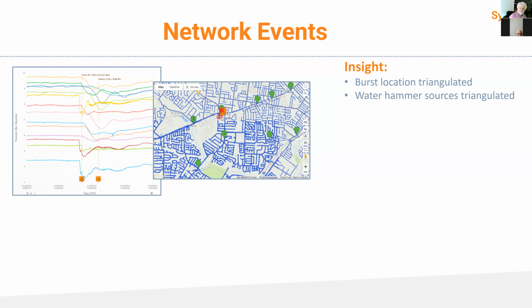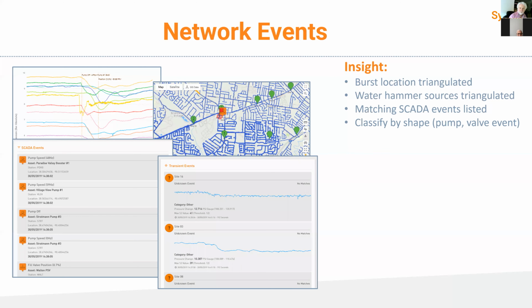The first step is we'll look at the SCADA data that we might or might not have, telling us what network activity there is. So in this case, you can see we've tagged a pump event. We'll then triangulate it, see if we can get a location. So we'll look for the onsets and triangulate the location. And then the last thing we do is look at the shape of the transient and compare it against a library of shapes. It's not a very good example, this one with the shapes, but we have good sets of sort of pump stops, which is a drop, maybe a ring, pump starts. So we can give you an indication of what we think just based on the shape the event is.